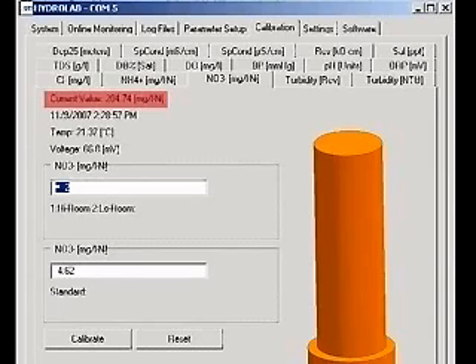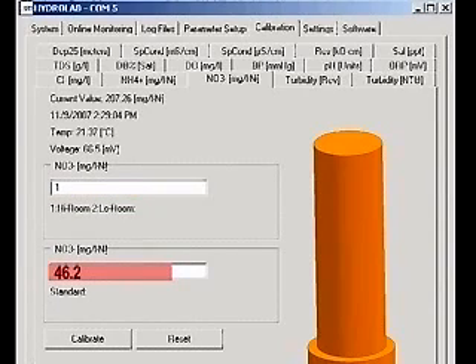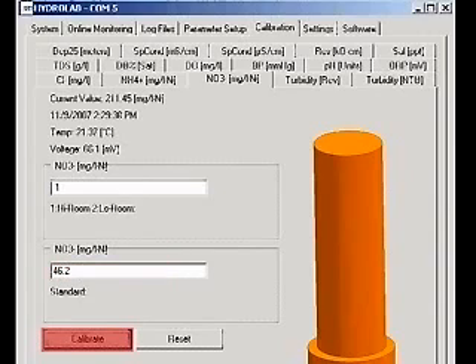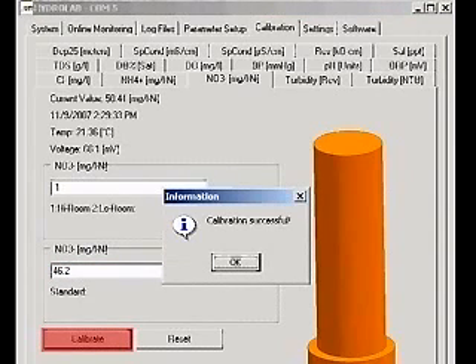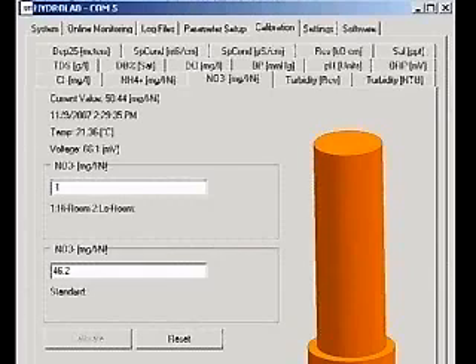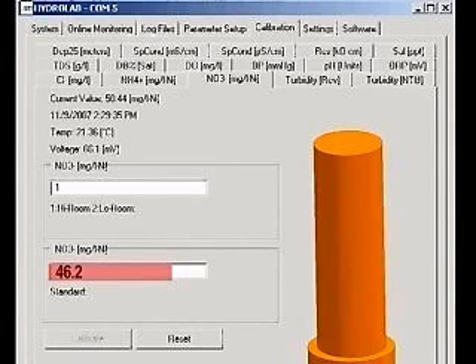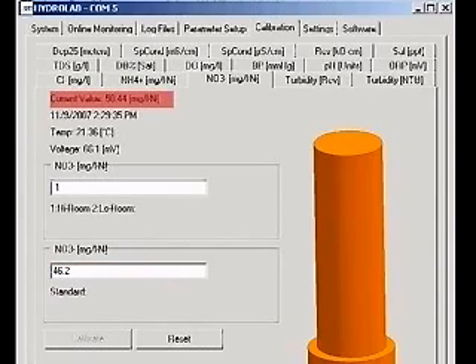When the readings are stable, type a value of 1 in the first box to designate the high standard. Type 46.2 into the second box and click Calibrate. A calibration successful message will appear. Record the temperature and the voltage reading. Note: the value typed into the box is the ion activity, but the value appearing in the current value display will be the ion concentration.